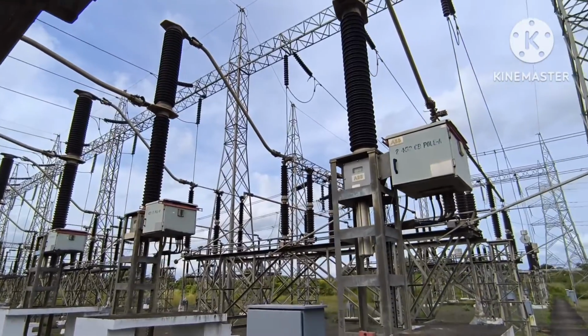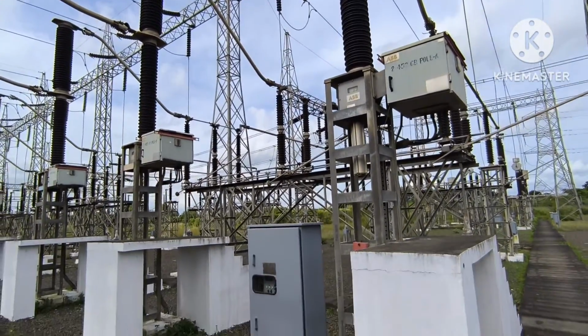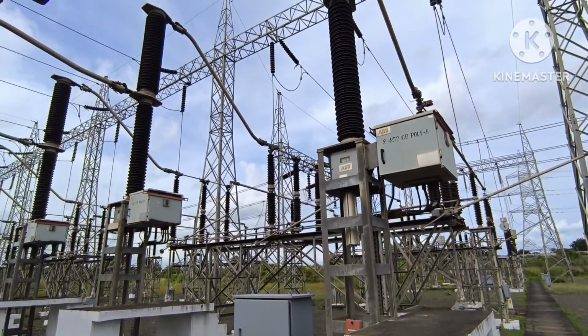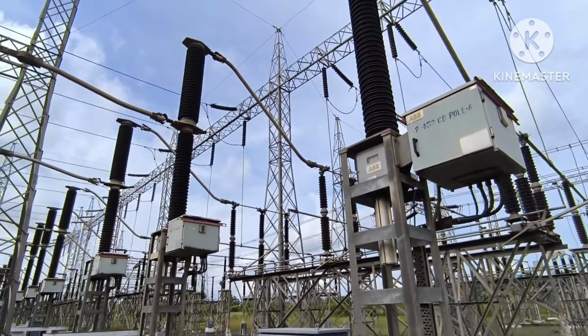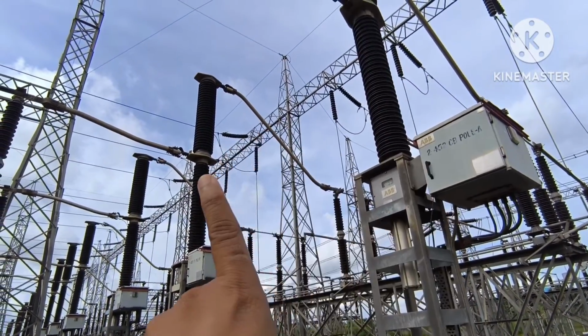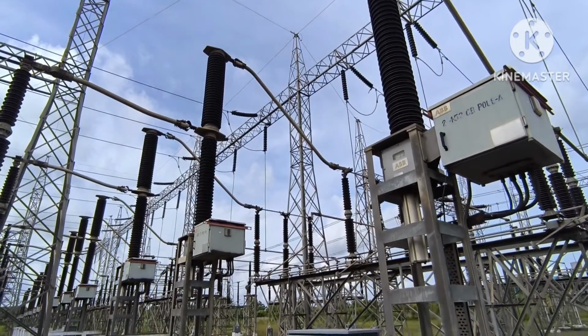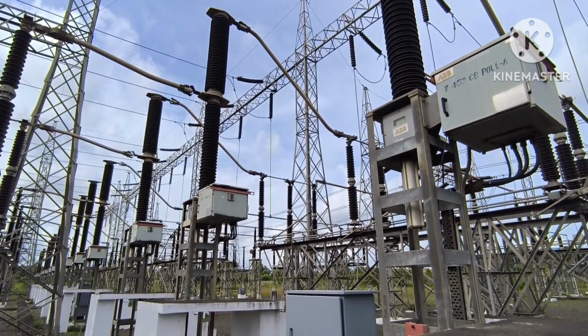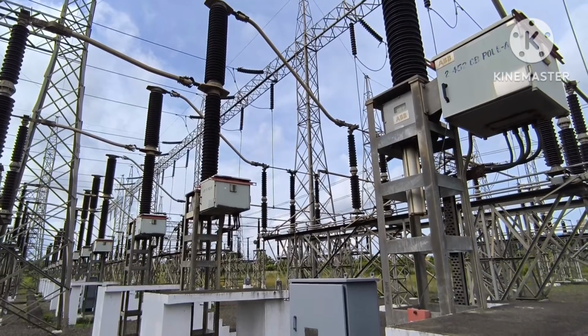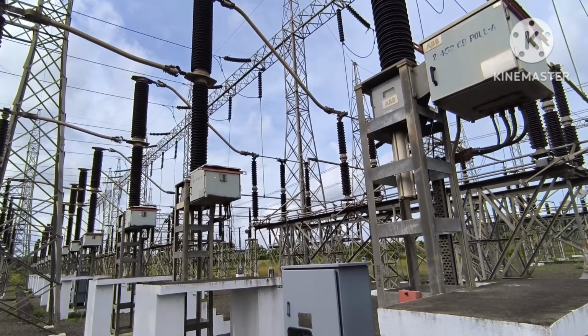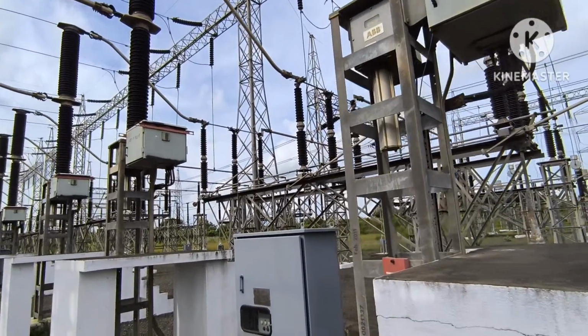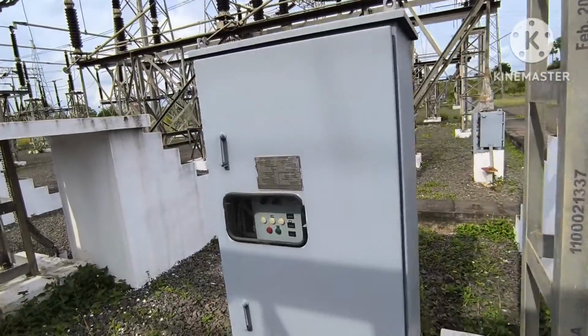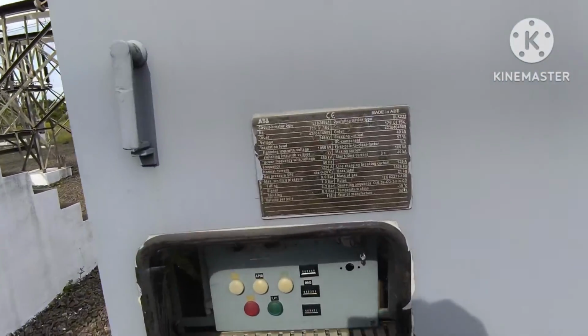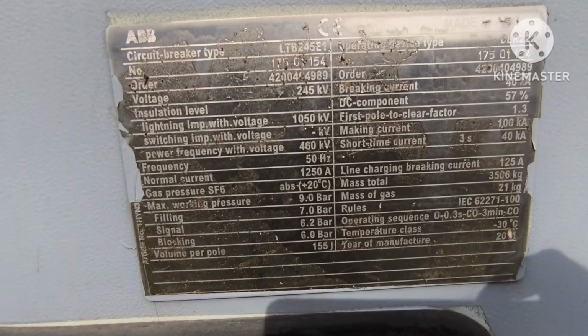It is independent pole operated. So each phase you will find one breaker. You can see this is R phase, Y phase and this is B phase. In each phase you will find one breaker, so it is an independent pole operated breaker. We'll see inside the marshalling box, but before that we'll see the nameplate details.